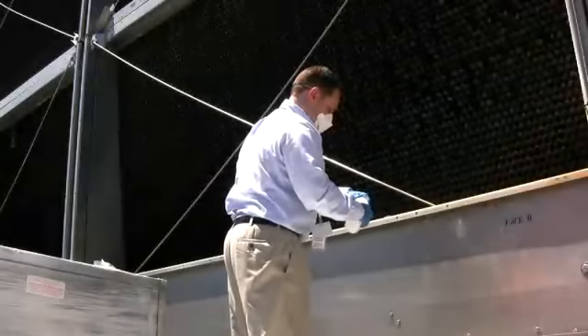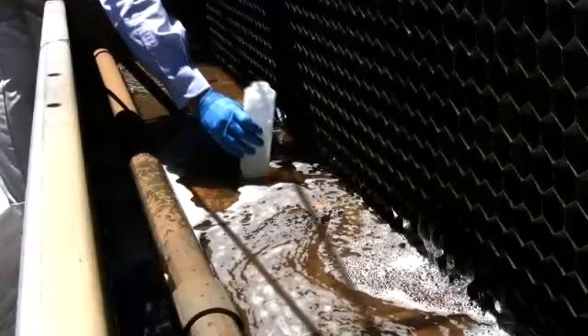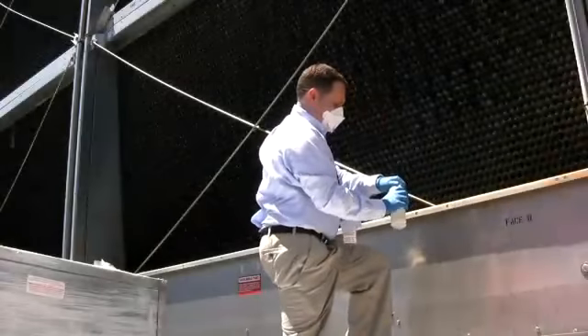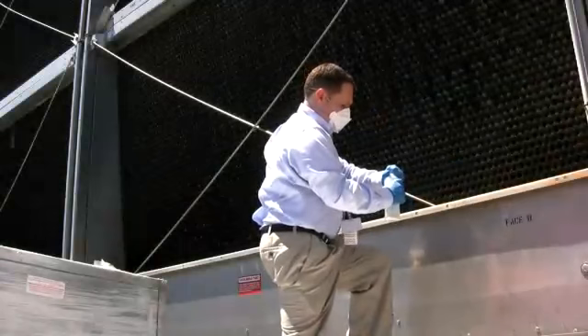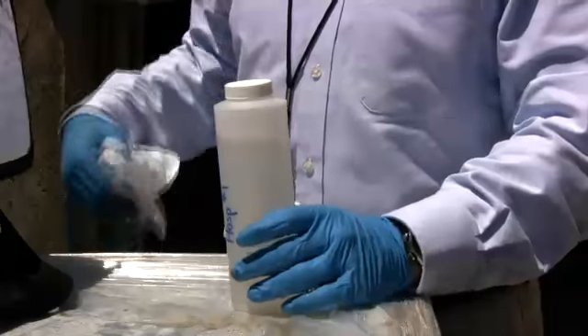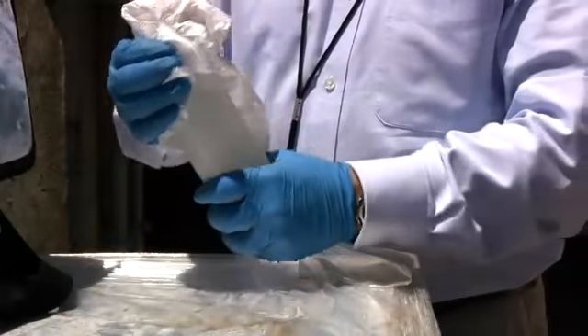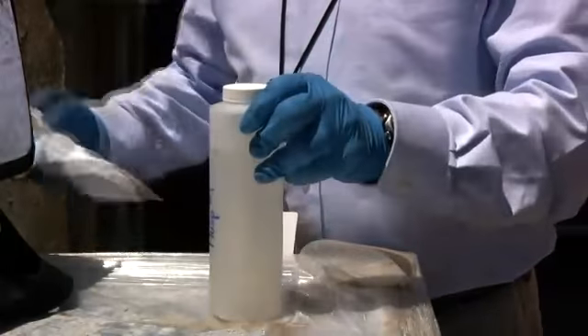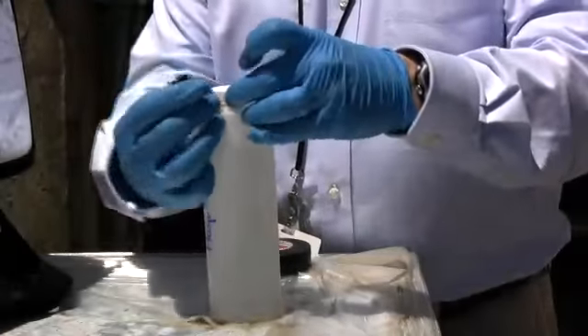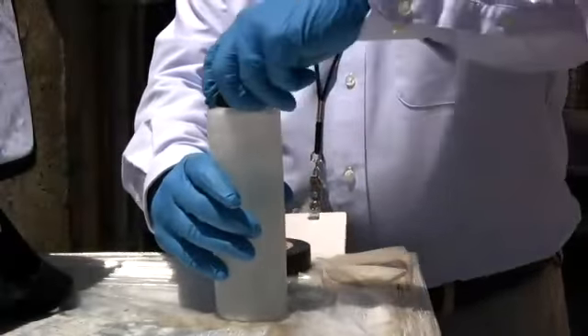When collecting a sample from a cooling tower, collect from the point furthest from any biocide feeds or pucks. Collect the sample from the basin if possible, or from the drain access at the lowest point. Dip the bottle into the water and fill to within 1 inch from the top. Do not fill the bottle completely. Once the bottle is filled, securely fasten the top, dry the bottle, and seal with standard electrical tape or Teflon tape. Ensure that all mechanical systems that were shut down are turned back on and that the proper personnel are notified. Verify the information on the bottle matches the chain of custody and prepare the sample for shipping.